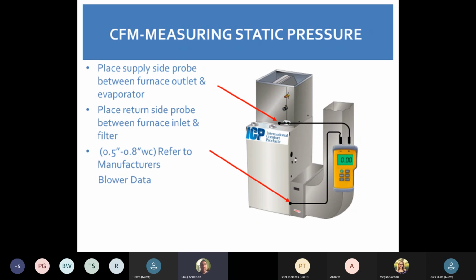If we're too high, then our motor is working too hard. So then we're going to have motor failures on furnaces. If you're going back, I've changed the motor twice in 3 years. We need to start looking outside the box. We need to make sure that our coil is clean, our filter isn't dirty, or we don't have the wrong filter in there. So static pressure is a big thing on the market right now because our motors, to meet the FER rating, need to be variable speed, they need to work off static pressure.